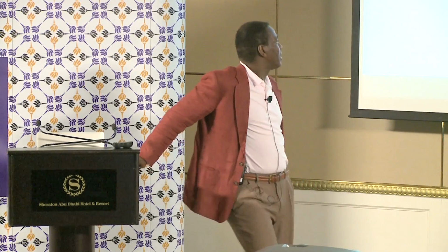Okay, so one of the things I didn't talk about here is if you want higher resolution, instead of even just going to using a lot of directions, you want to go to high field strength. So the highest clinical field strength right now is 3 Tesla. Now, for comparison, the Earth magnetic field, depending on where you are, is about 0.5 Gauss, which is very, very small. So 3 Tesla is a big field, but the kind of fields I'm working on is about 21 Tesla. And that gives you a lot more resolution in terms of tracks that you can see, issues you can resolve, but it's all done with much more cooperative patients.